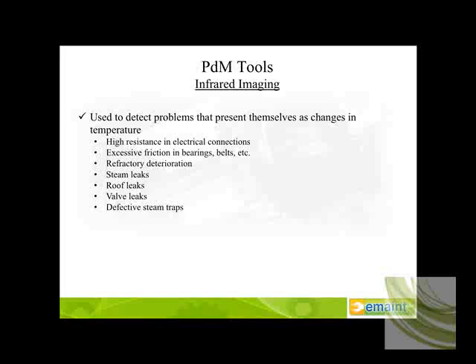One of the things I want to make sure that I do remember to point out here, in assessing any type of PdM program and the use of thermography, is to make sure that you take your arc flash requirements into consideration when using this tool. The reason that we say that is that infrared cameras cannot see through anything. So primarily, low voltage cabinet doors need to be opened while the inspection process takes place. And therefore, we need to make sure that we are very cognizant of our arc flash ratings, arc flash requirements, personal protective equipment that must be utilized when performing those types of inspections on electrical distribution systems.